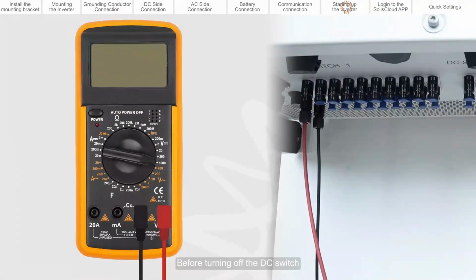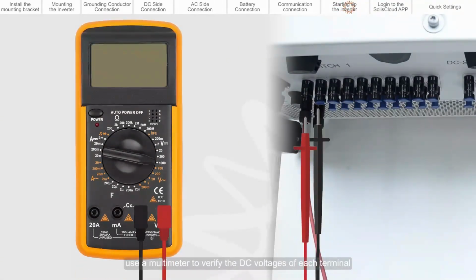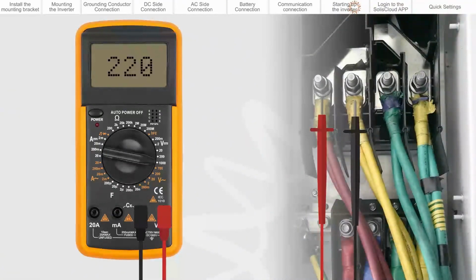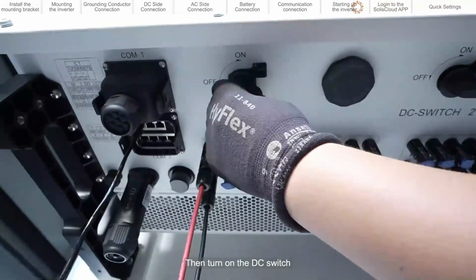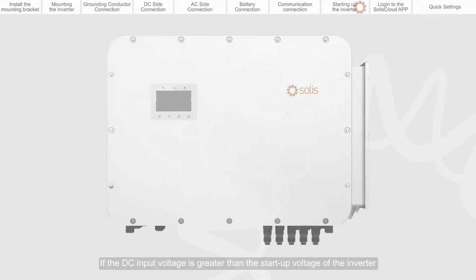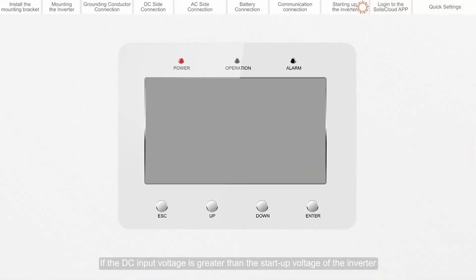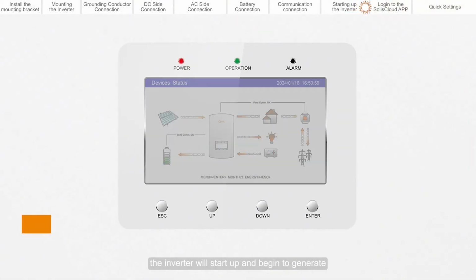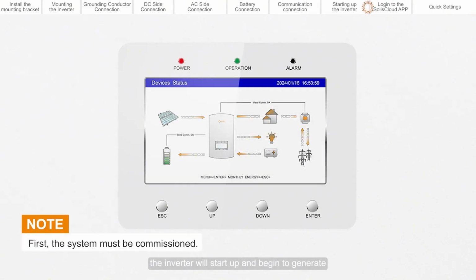Before turning on the DC switch, use a multimeter to verify the DC voltages of each terminal. Then turn on the DC switch. If the DC input voltage is greater than the startup voltage, the inverter will start up and begin to generate.